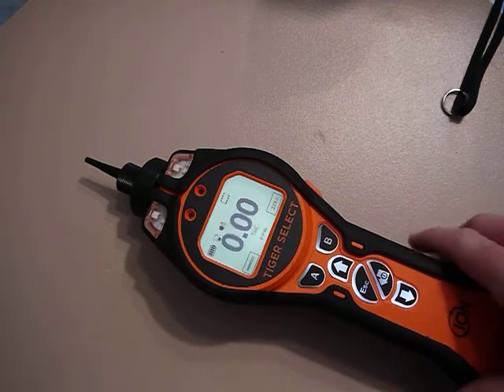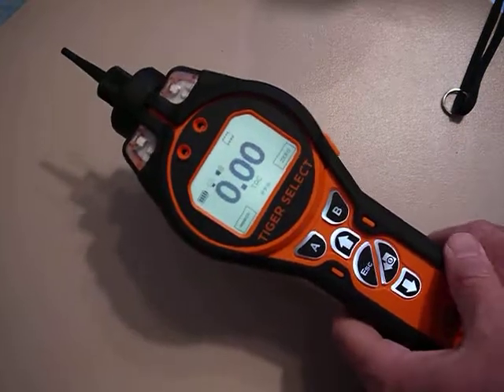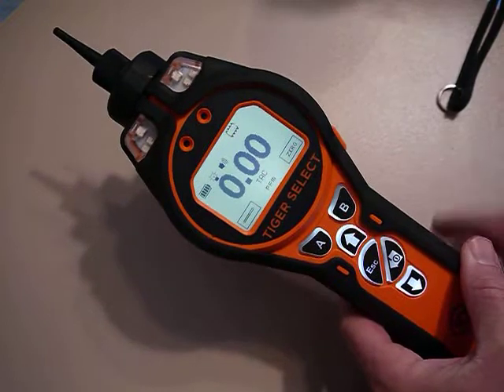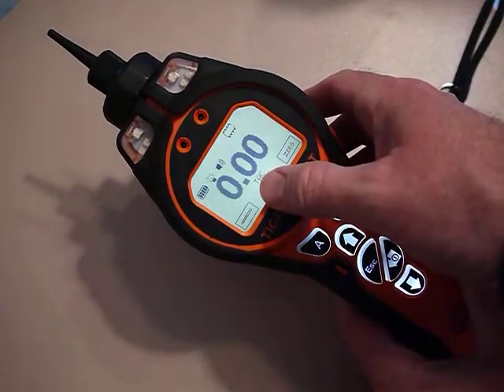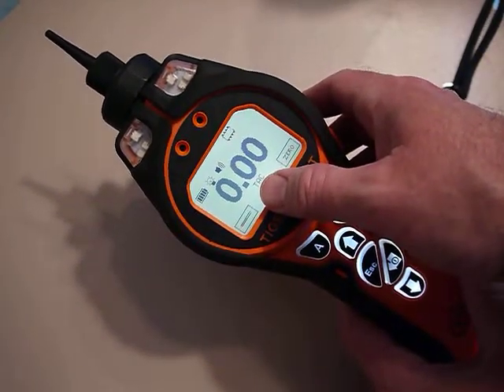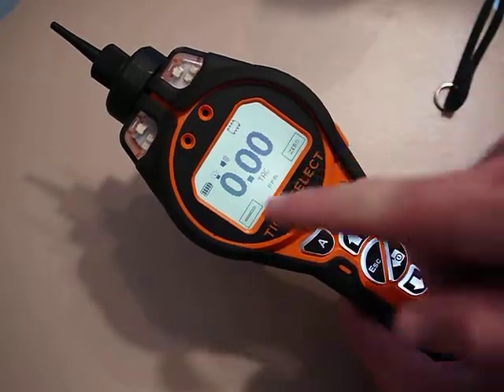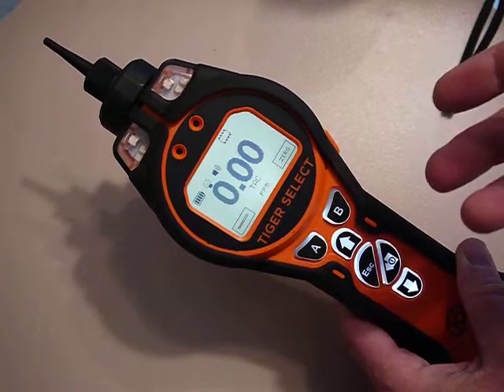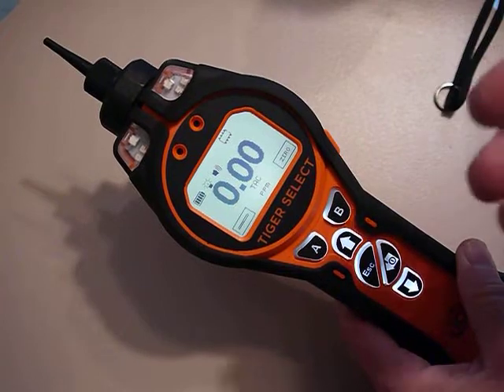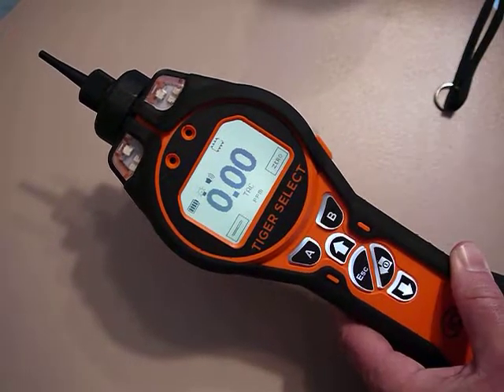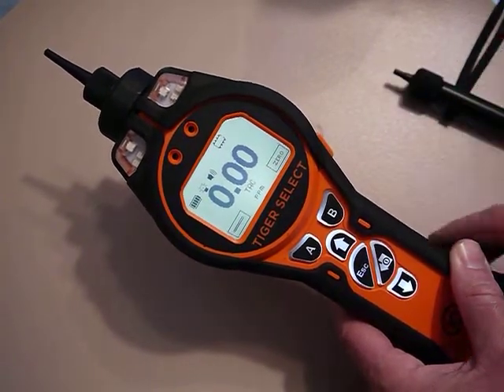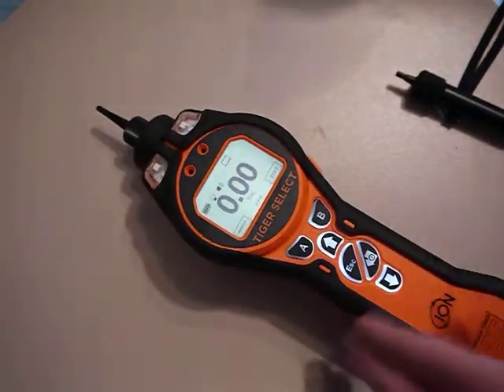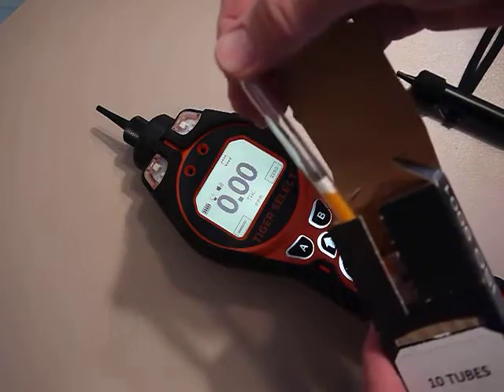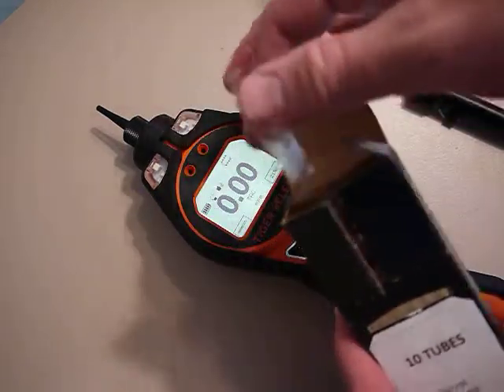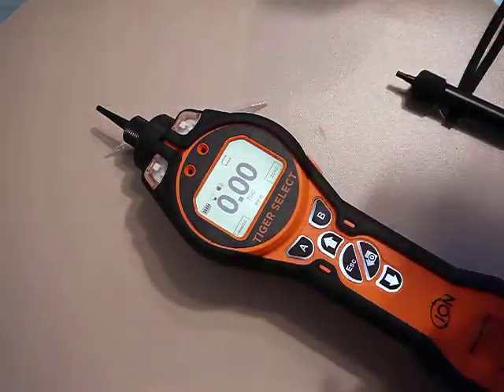In my last video I showed you how to calibrate the Tiger Select with isobutylene and put it into TAC mode, total aromatic compound mode, to screen for things like benzene. So if I did get a high reading when I was out taking measurements and I wanted to take a real measurement of benzene, that involves using a scrubber tube. Tubes like these will be a pack of tubes included with the unit. But first I need to calibrate to benzene, and I need to calibrate to one of these tubes.